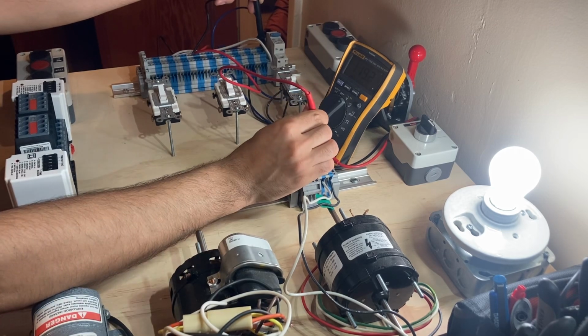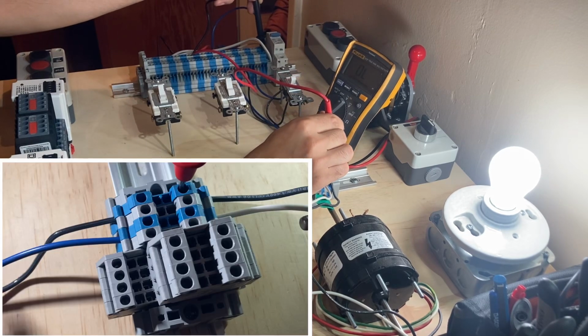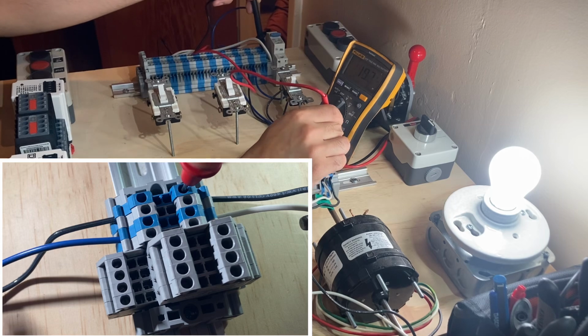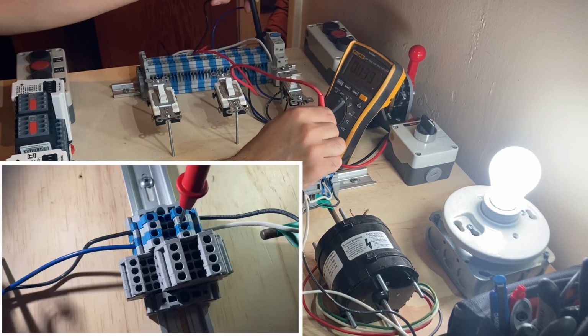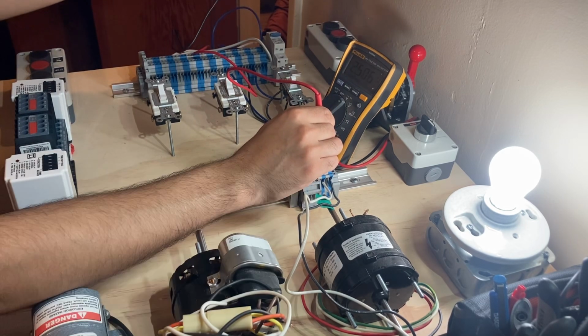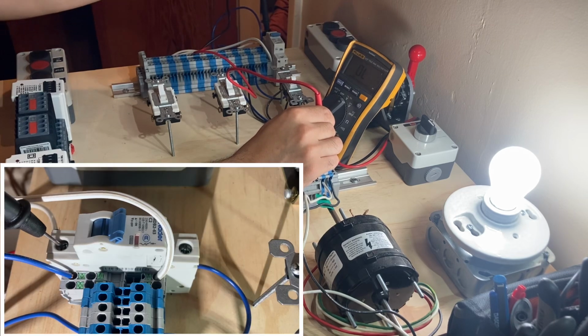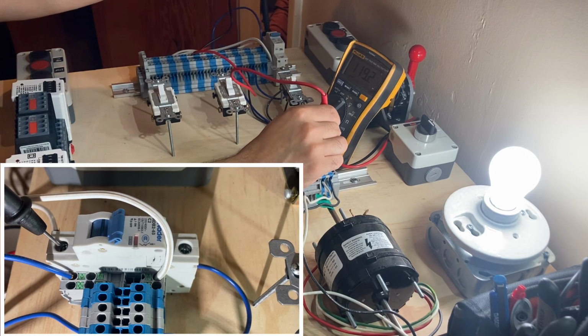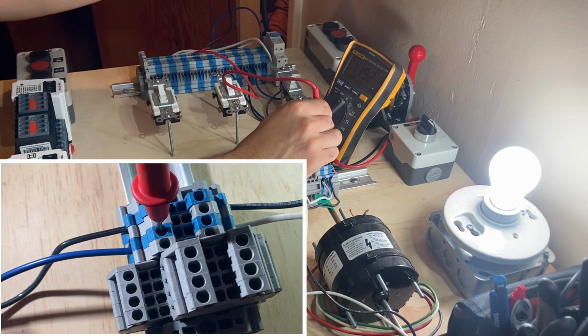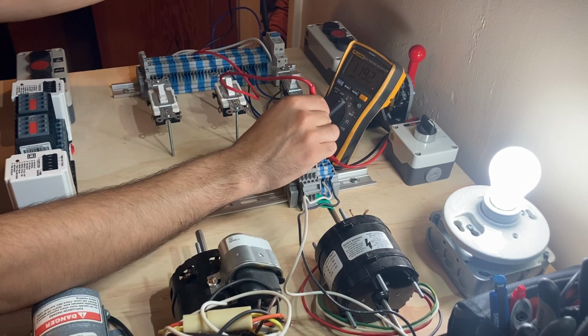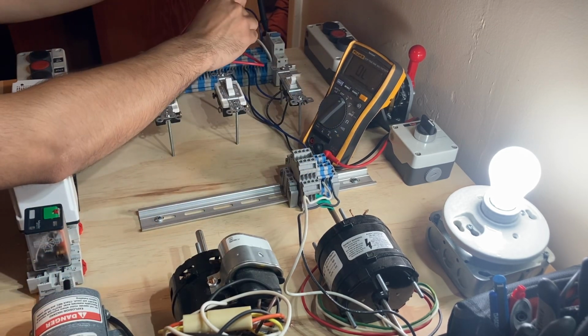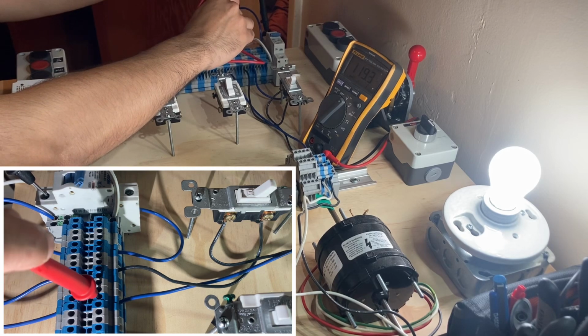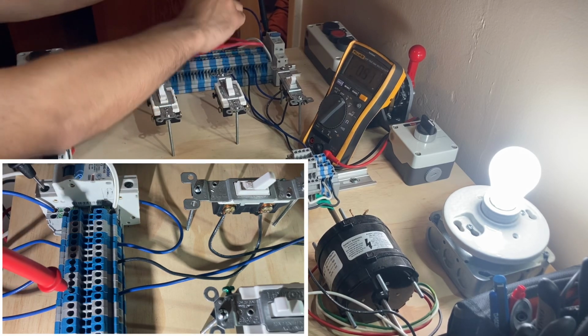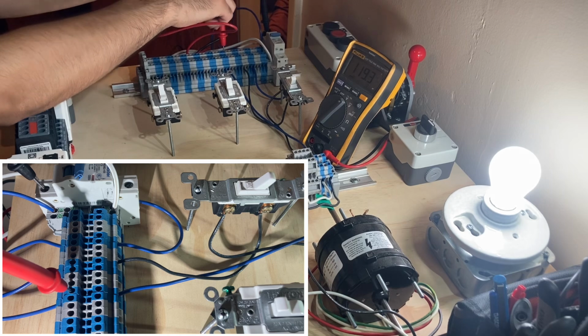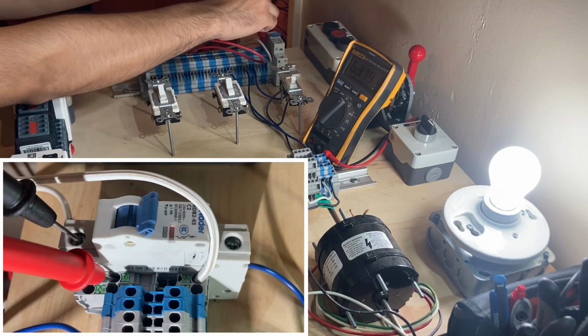Continuing along now again, remember I have my black lead on my neutral. Now I'm on the neutral side of the light bulb. So I put my red lead on my circuit breaker, my line side, to read the 120 volts. Remember, you're only going to read 120 when one lead is on your line side and one lead is on your neutral side.